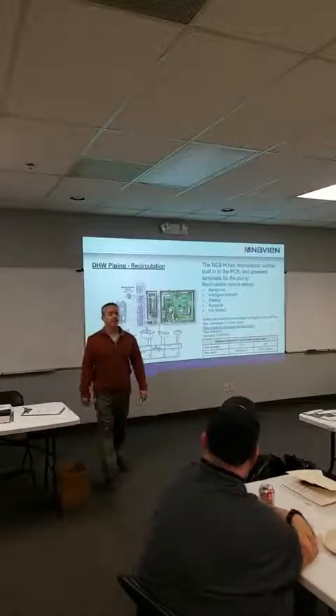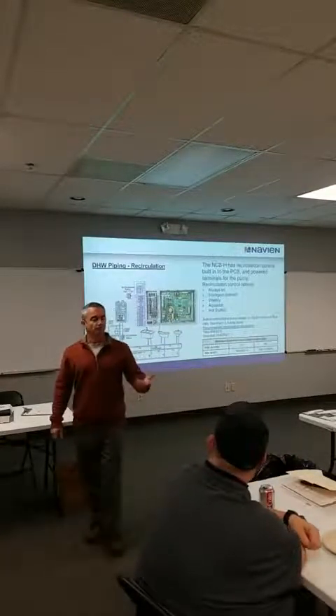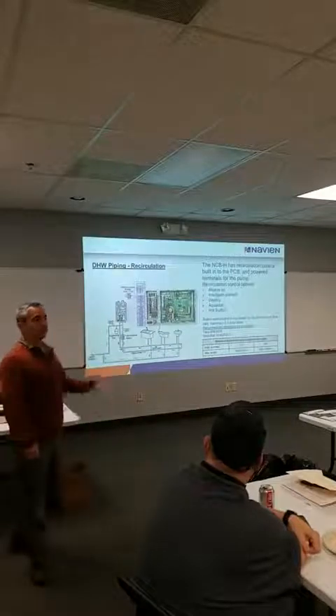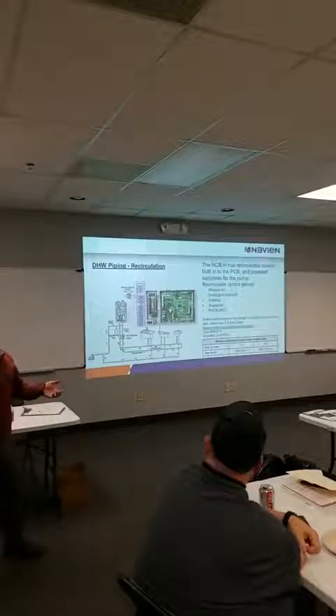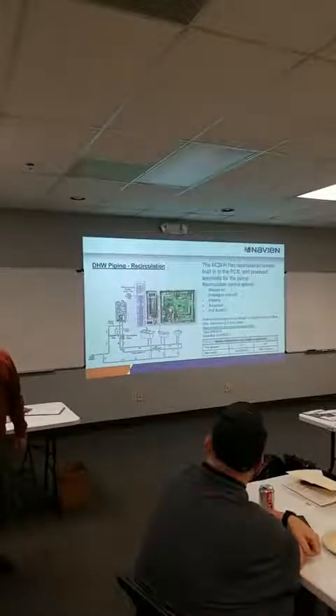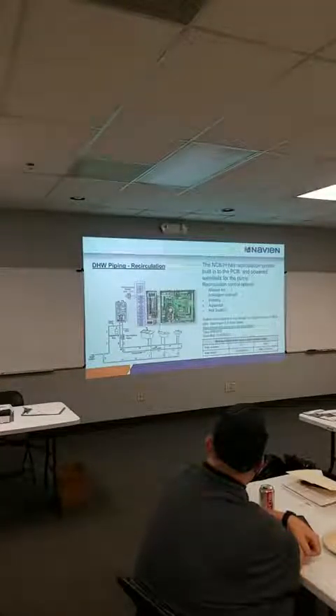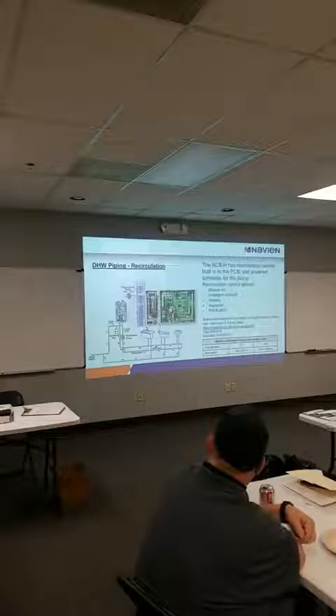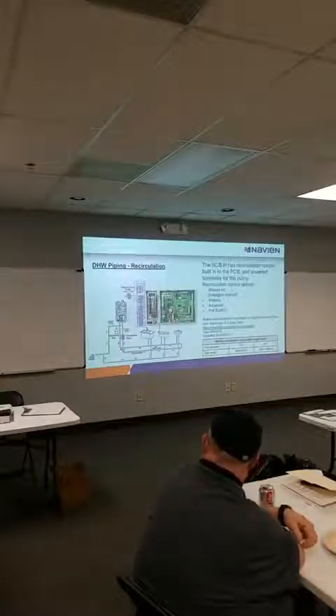So you can schedule it too, to say, like, morning hours before everybody wakes up. Exactly. If somebody doesn't want to run the pump all day, or if you just don't want it to run certain hours, you can do it in half-hour increments throughout the day. When you're wiring back to the boiler and a recirc pump, is it taking completely away from the heat when it goes into recirc?